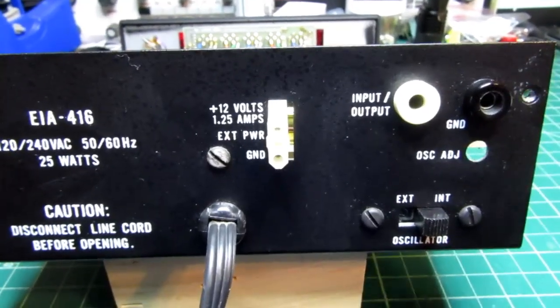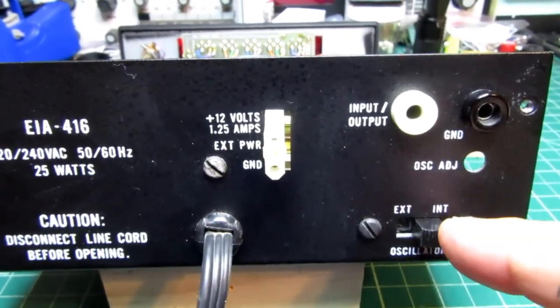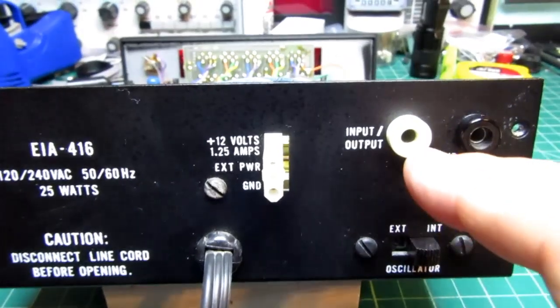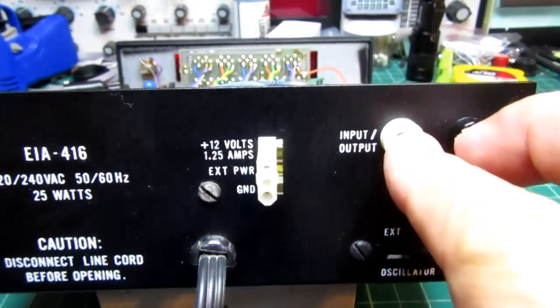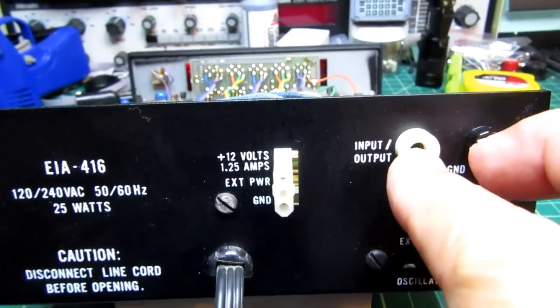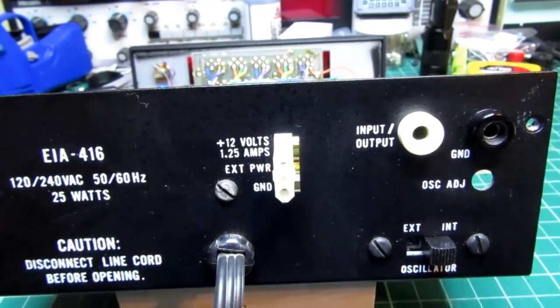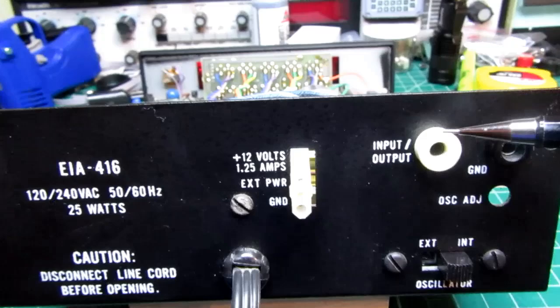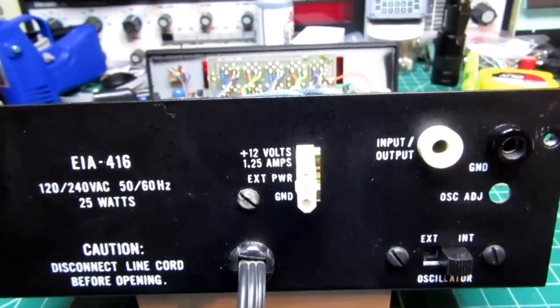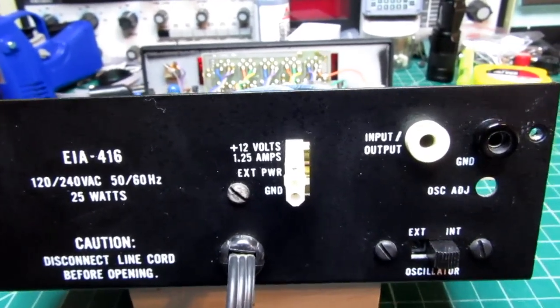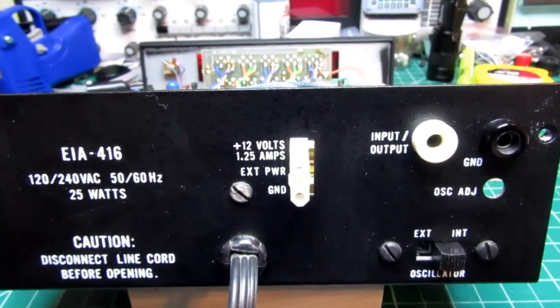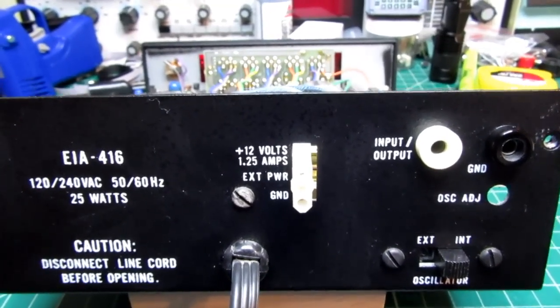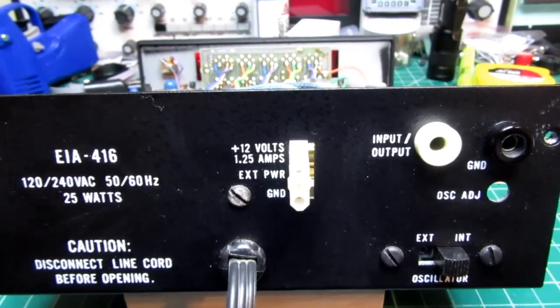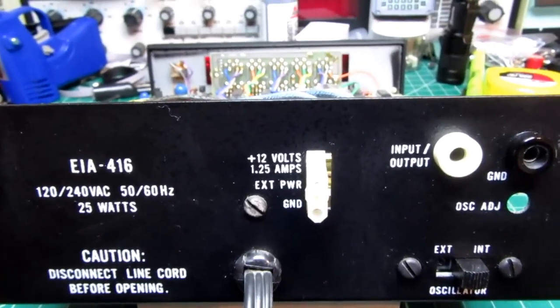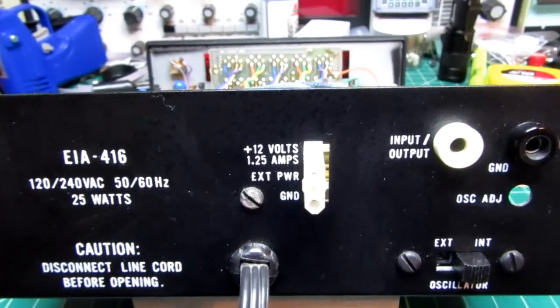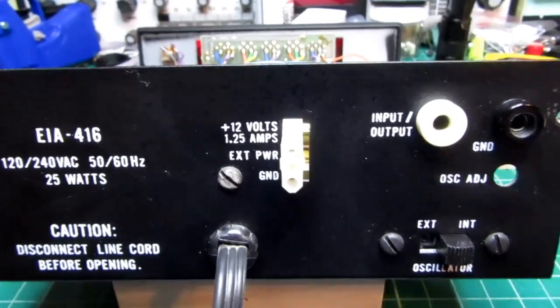You still have to select this to external, and you can connect anything up here. It could be a switch, it could be a TTL logic signal, but the totalized mode counts input pulses coming in through the normal input jacks, and it keeps counting them indefinitely until you either overflow the counter, or you reset it, or you stop it, either permanently or temporarily. And that's what these jacks are used for in that case.